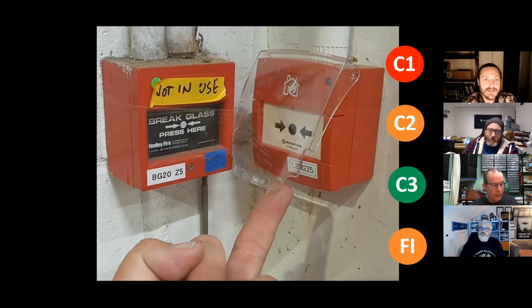Yeah. And again, Dave, I think a lot of people will argue with me on that, which is fine, but you wouldn't install it like that on day one. And that's not something that's just been degraded over time. That was installed like that. I think it's a case of trying to understand the conditions which the wiring system is supposed to actually be designed for. Having FP alone doesn't automatically mean it's completely impervious to a fire incident if the structure and everything else is going to collapse around that and pull it down or damage it, isn't it?